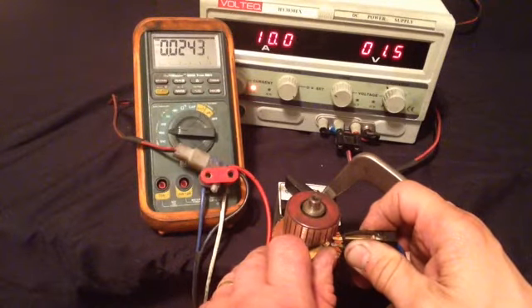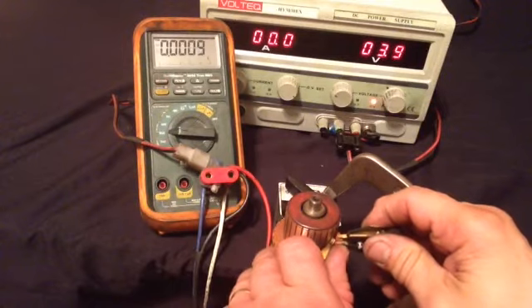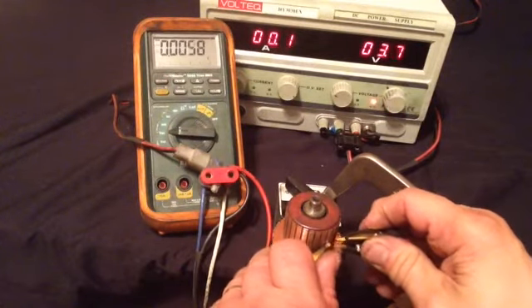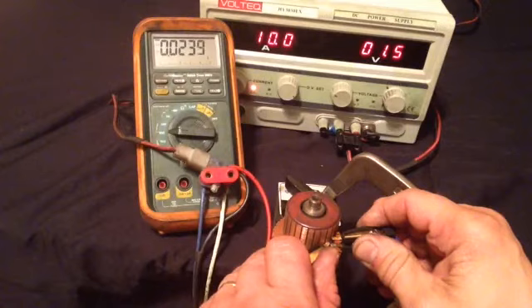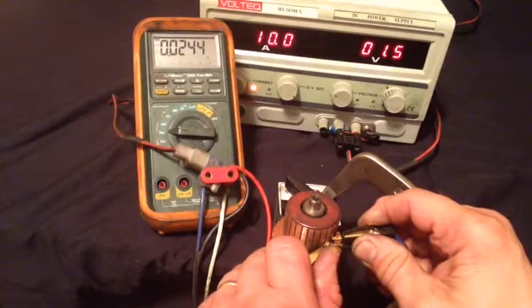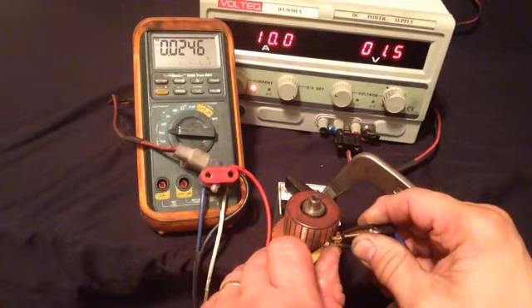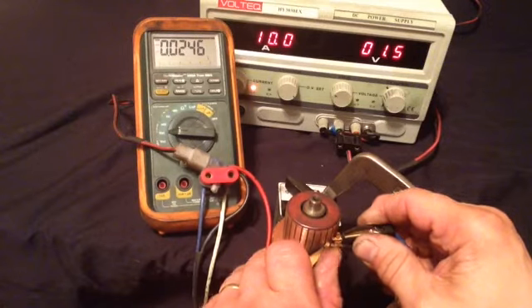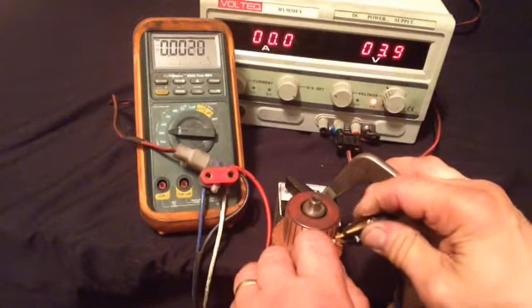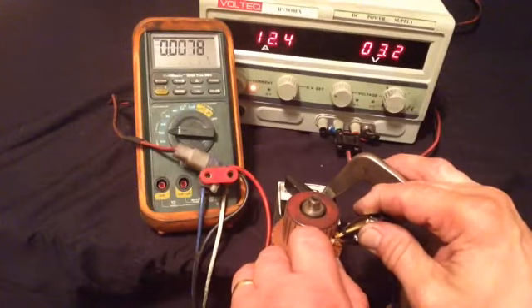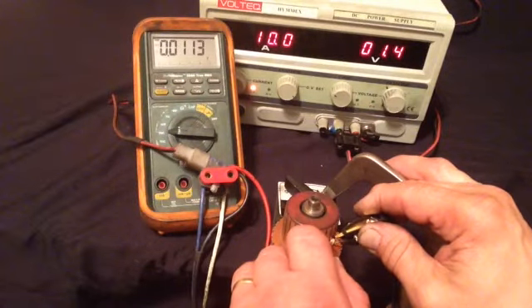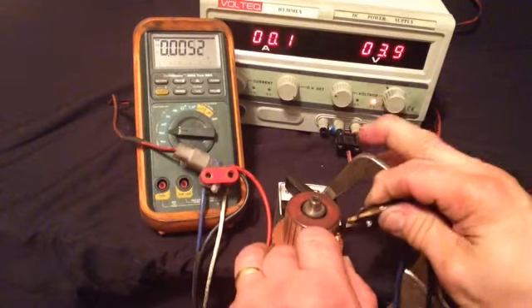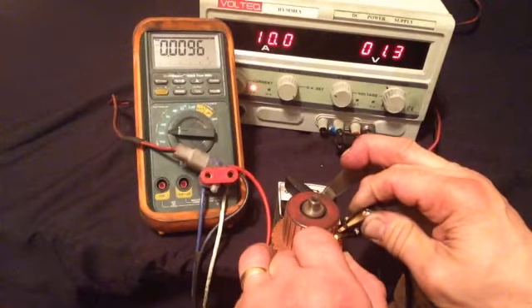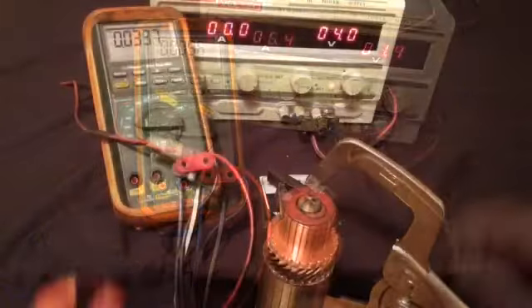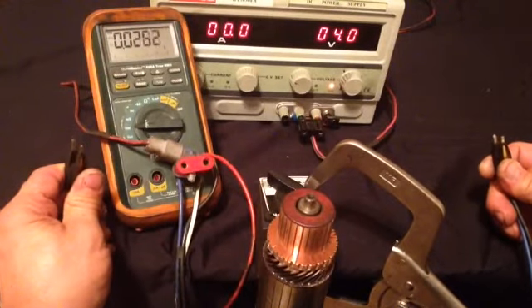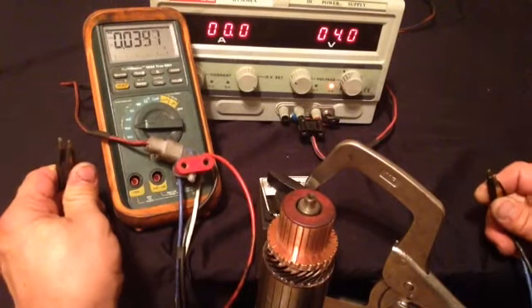Now here we have 0.02. It's over twice what the normal connections are. So that connection there is a bad one. It's probably open. And then after that, it goes back down. It's a little high still, 0.011. But going further, it's back down to normal. And that is how you test a commutator for good connections.